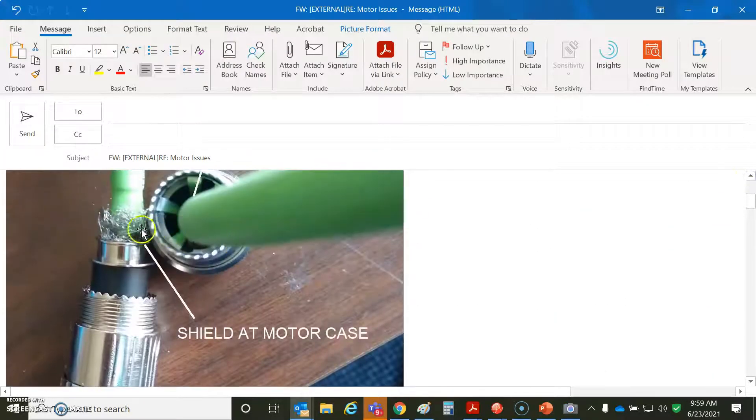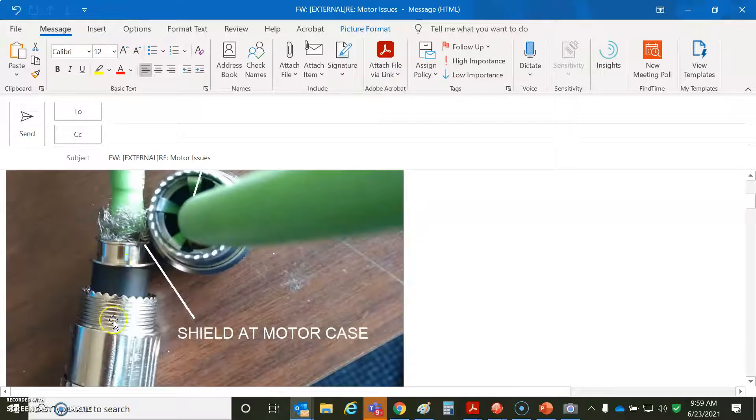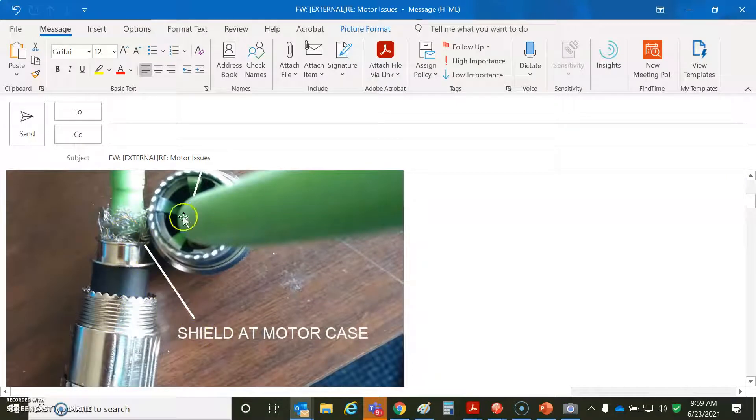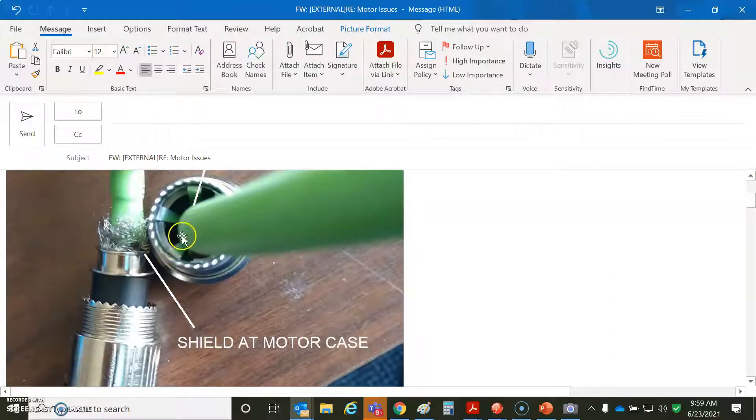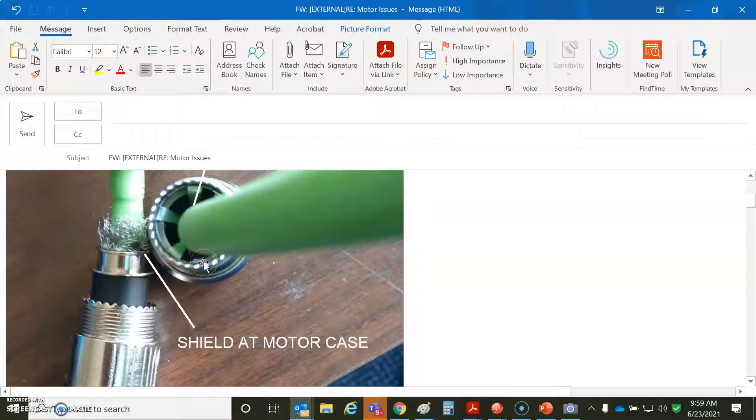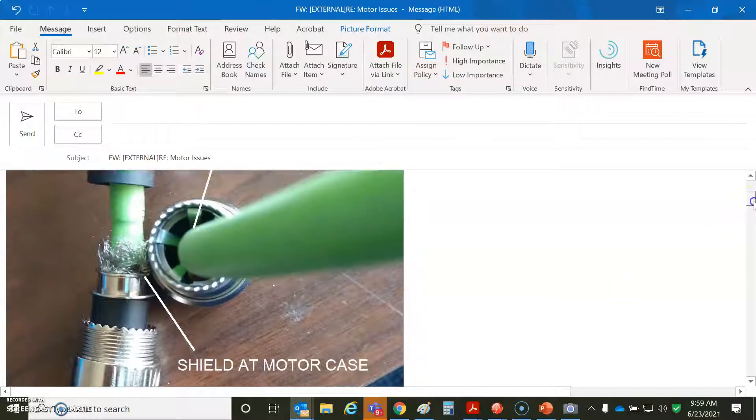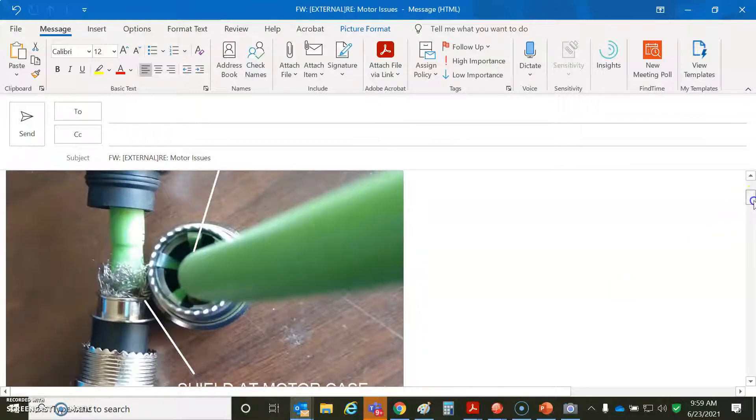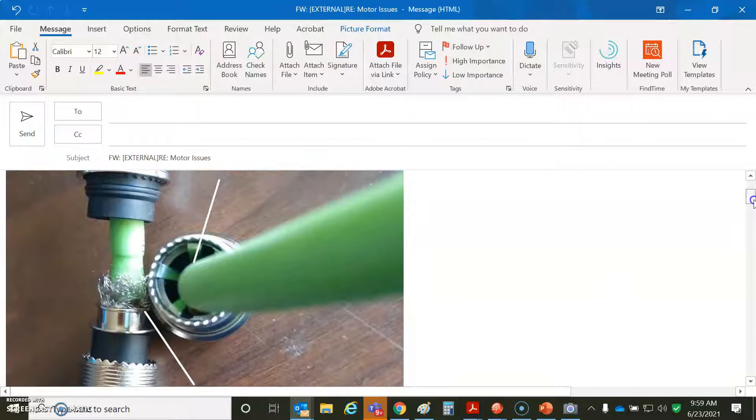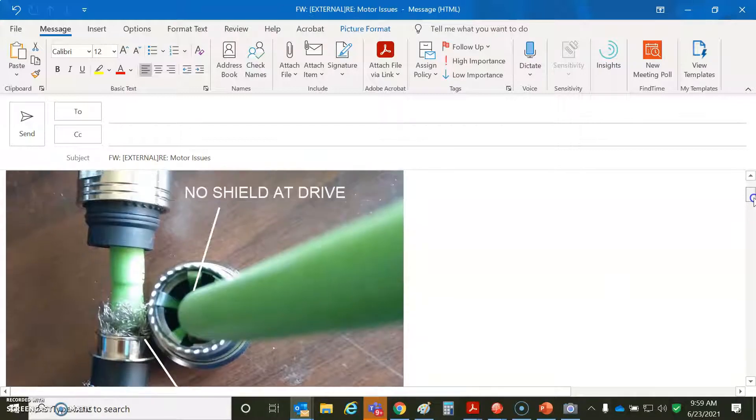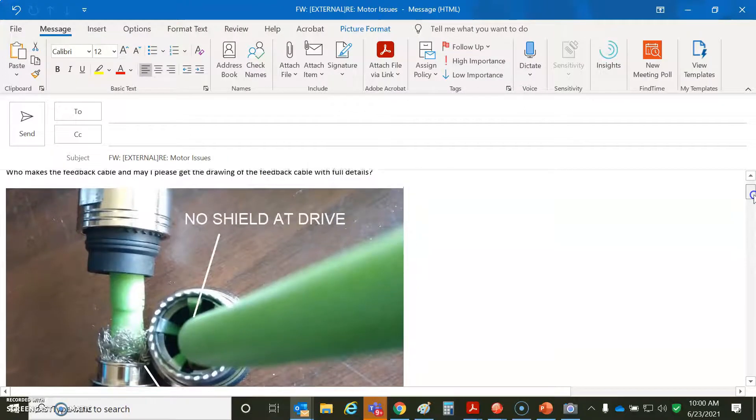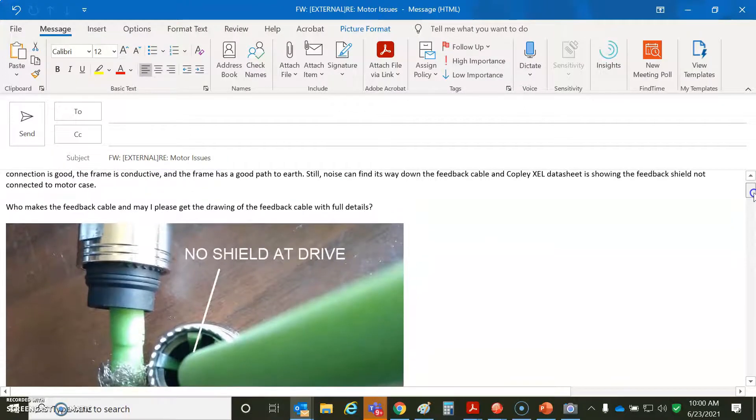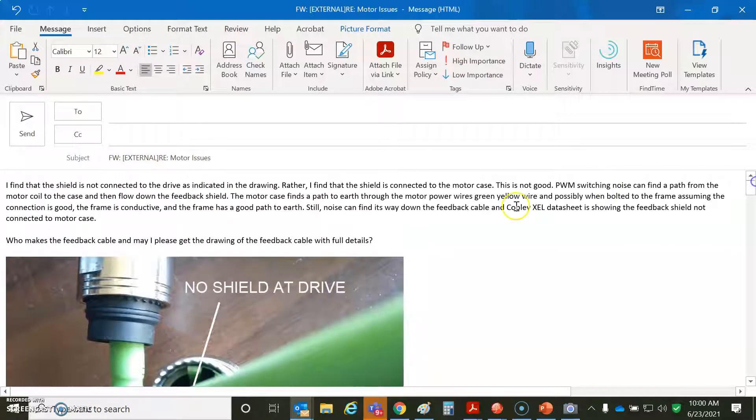And if you want it a little better, the inner braid goes to the ground. But that's irrelevant. But this is the important thing. At the motor, the shield is connected to the motor case. And then at the drive, which is this end, it's just all green in there and there's no shield pulled back. So no shield at the drive end. So I'm going to say this is the source of the noise, not that it's very much noise, but maybe this is, you know, if you had a poor path to earth for the motor case, or maybe something wasn't quite connected right, you could blow up the drive.